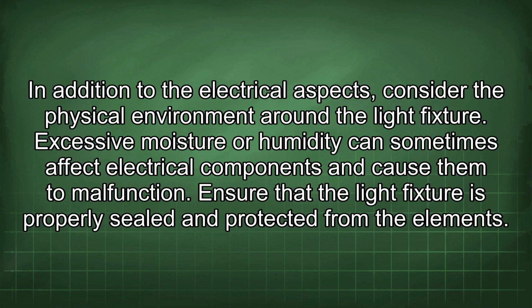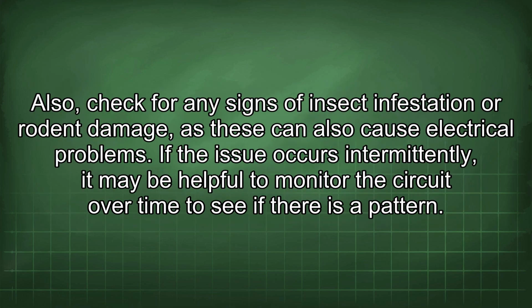In addition to the electrical aspects, consider the physical environment around the light fixture. Excessive moisture or humidity can sometimes affect electrical components and cause them to malfunction. Ensure that the light fixture is properly sealed and protected from the elements. Also, check for any signs of insect infestation or rodent damage, as these can also cause electrical problems.